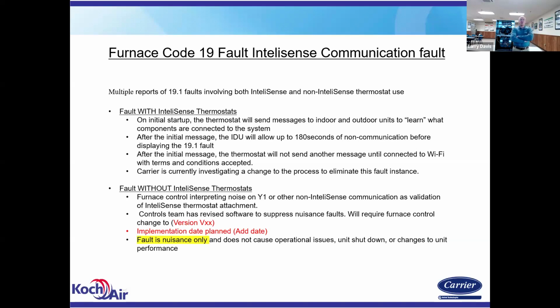We were getting some nuisance faults saying, hey, either we don't see a temperature, or there was basically some noise on the Y1 circuit for some of the non-IntelliSense thermostats. There's a software version update for the boards, but unfortunately, you have to change the board out because it's non-communicating. That fault's a nuisance only. It's just in there. It does not affect the operation. You don't even have to hook up the temp sensors. It'll run all day long without them. So that's up to you. Really no need to change the board to eliminate that fault unless it's just a pain for you. By the way, that fault does not communicate to the thermostat. Homeowner has no idea. It's just on the board.